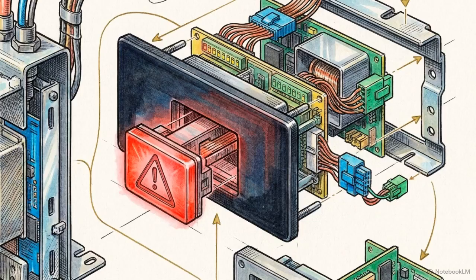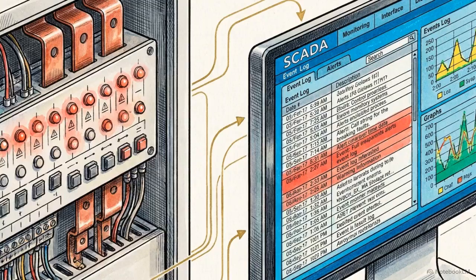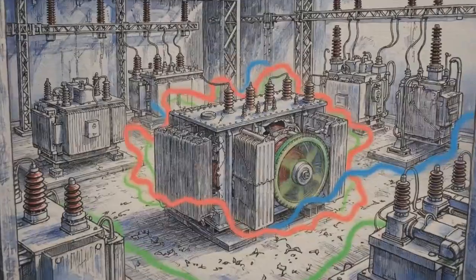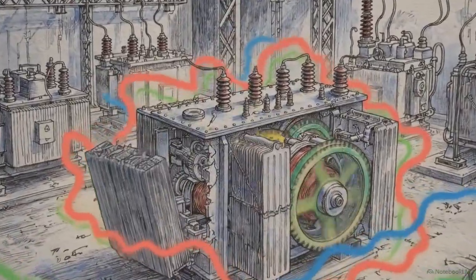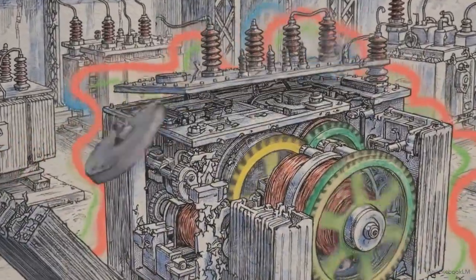Then validate the alarm matrix. We do this by simulating on-load tap changer, or OLTC, alarms. Track each simulated alarm, such as an AC/DC fail or a Buchholz trip, directly to the SCADA system to verify accurate remote feedback. Failing to clear these interlock hold points risks causing an immediate transformer out-of-step condition, which would render subsequent relay logic testing ineffective.